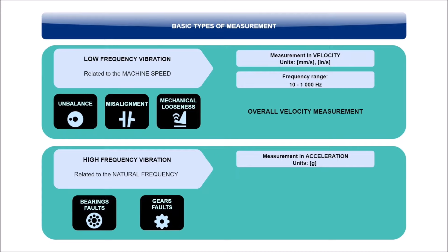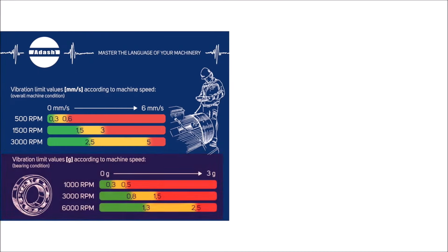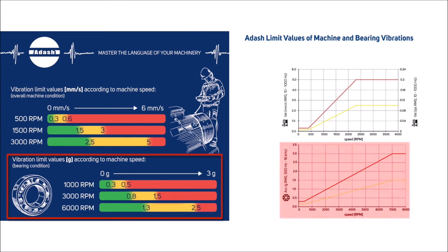But let's keep it simple, and define your measurement of acceleration in the range of 500 to 16,000 Hz. ADASH has defined bearing vibration limits related to the speed of the machine again. The mentioned frequency range of 500 to 16,000 Hz has been applied.